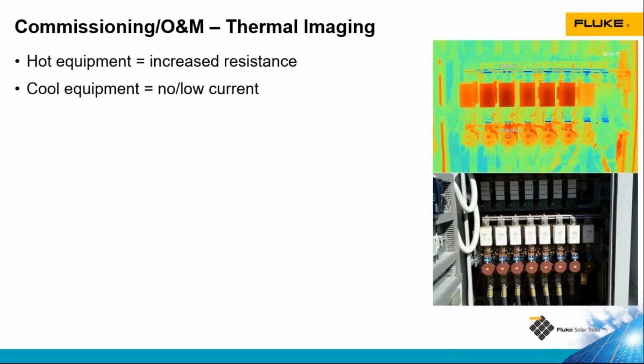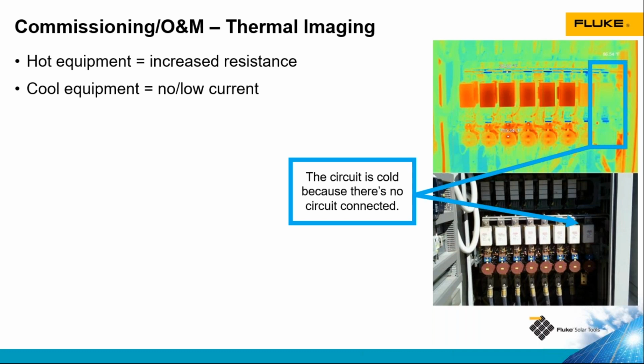Now, when we're doing thermal imaging, we're not usually looking for a specific temperature. We're looking to see how different pieces of similar equipment vary in temperature under the same environmental conditions. If a piece of equipment is hotter than other pieces of equipment, that could indicate that there's high resistance in that circuit. Maybe there's a loose connection. We can also look for things that are cooler than other pieces of equipment. The picture we have here, the right-hand circuit is cooler than the rest of the circuits, and if you look closely at that bottom picture, the circuit there does not have a wire connected to it, so of course there's no current flowing through that circuit.